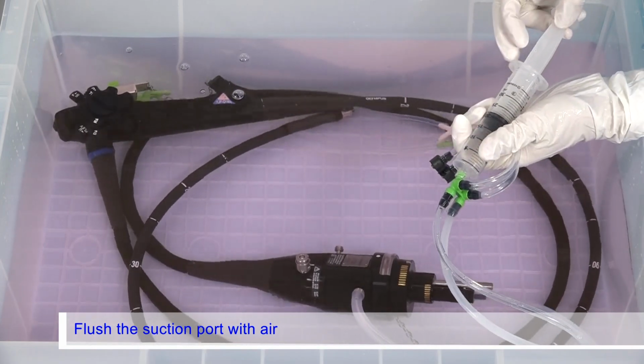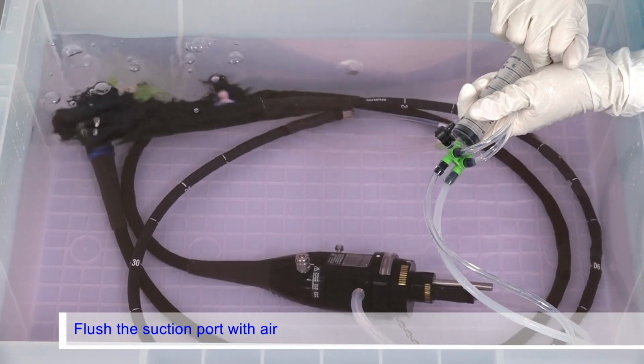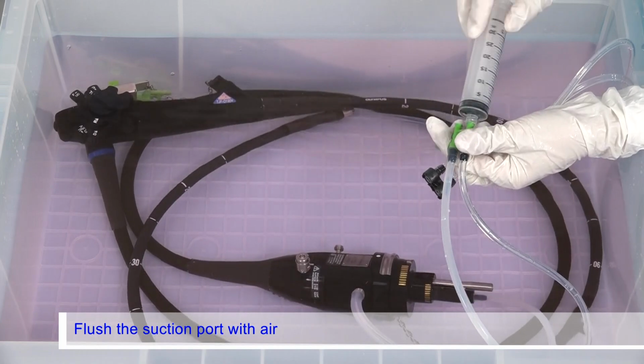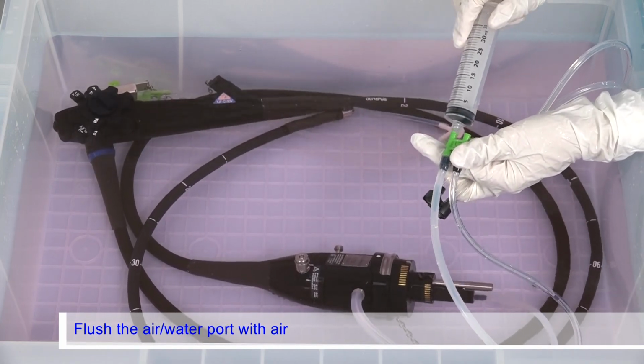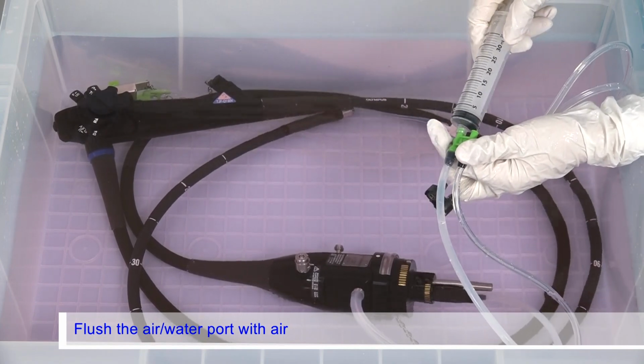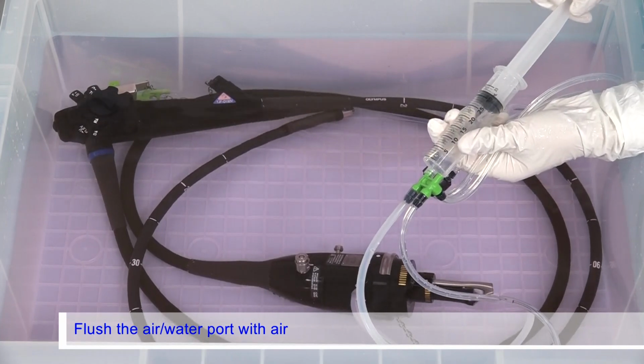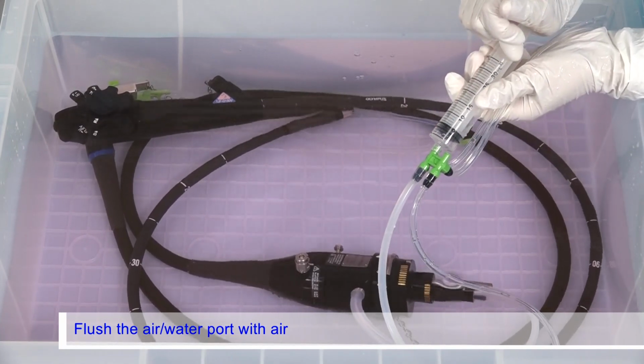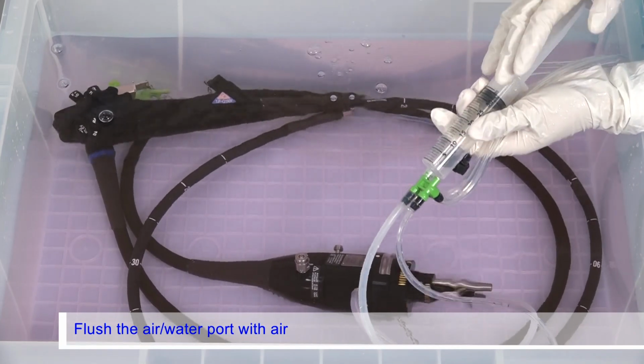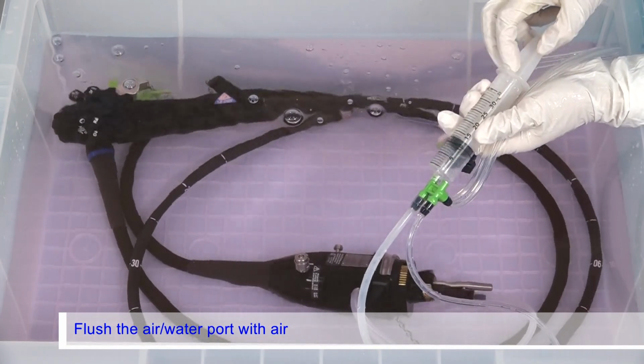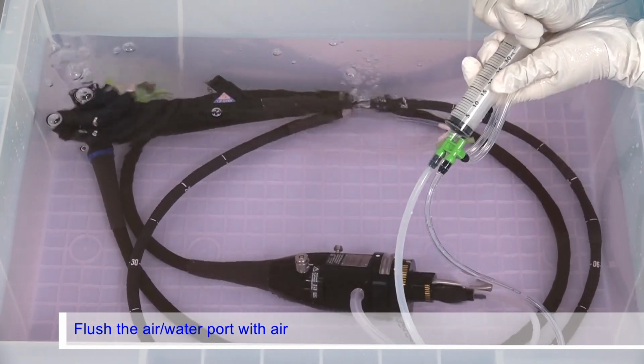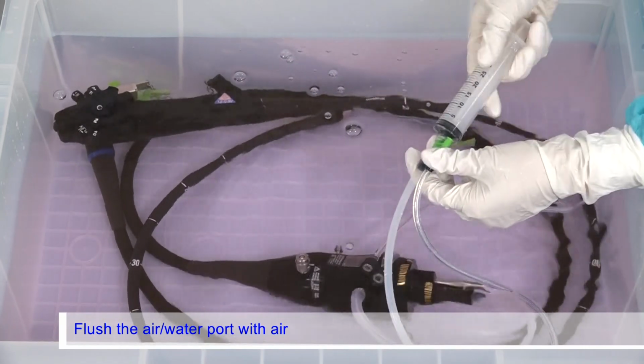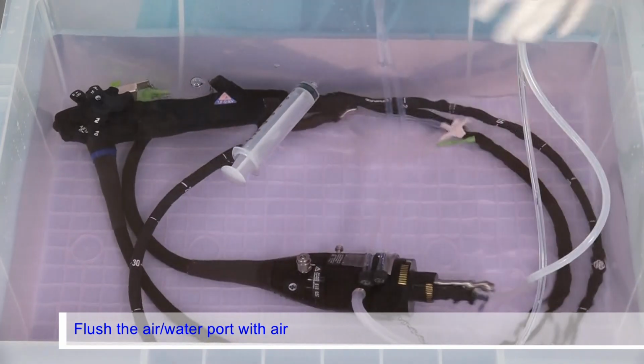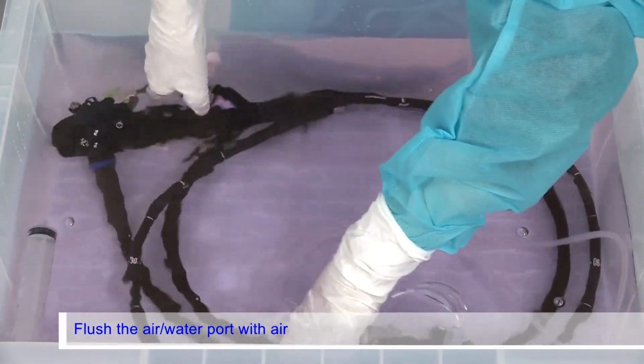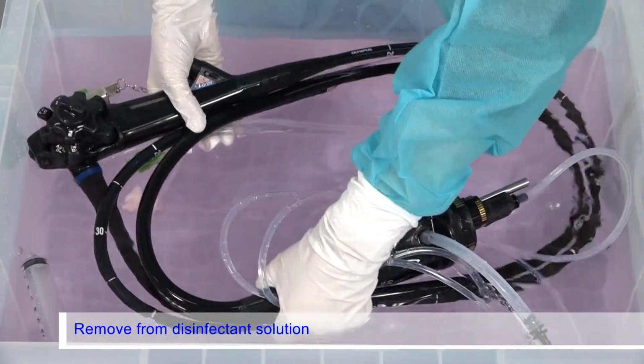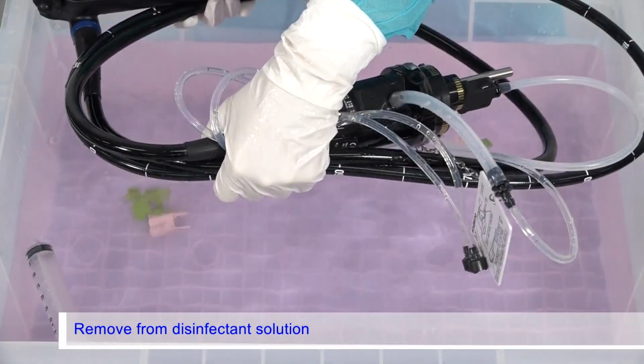If air bubbles do not exit from the distal end during the third flush, flush the channel with air until air bubbles exit. Move the syringe to the air-water channel port of the injection tube and pull the syringe plunger to fill the syringe with air. Then push in the plunger to flush the air-water channel with 90 milliliters of air. Remove the endoscope from the disinfection solution with accessories attached.